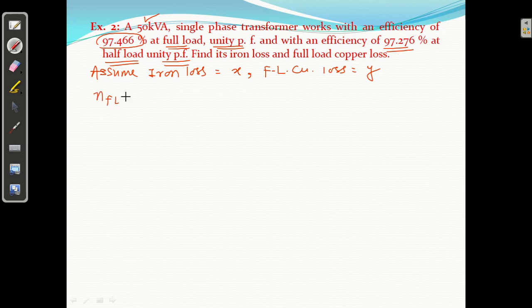Efficiency at full load is given as 0.97466. This equals output upon output plus iron loss, which is X, plus full load copper loss, which is Y, at full load KVA rating of 50,000 with power factor 1. So I got it, and no need of multiplication by 100 because I am not going to write 97.466.